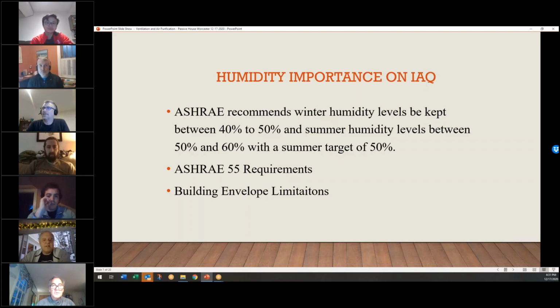So it's definitely something. If you're going to put them in, you want to maintain them, and you really need to consider the building itself, because older buildings probably can't handle the humidity. Like where we were, Salem Housing, the existing building, those old windows, if you tried to put 40% humidity in there, they'd be raining all over those windows, right? Those aluminum, non-thermally broken. So you have to be careful with the humidity getting pushed into the wall and creating dew points inside the wall.